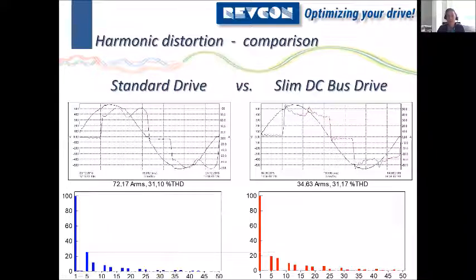On the left side, we see the standard drive. You see this more or less normal camelback on the current shape. And on the slim DC bus drive, the red one, you will see a completely different shape of the current. This is caused by a different spectrum. Both of these drives will cause you a THDI of 31%, as you can see right here. But the spectrum is completely different. Looking at these diagrams, the difference doesn't seem so small. In fact, this area is much more distorted on a slim DC bus drive. And the phase angles of the individual harmonics are also different.